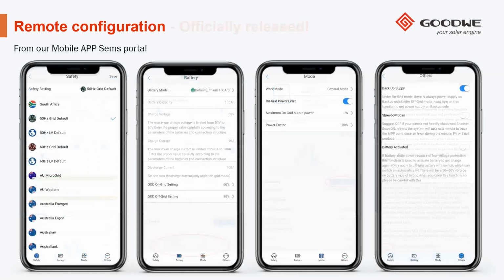From there, you'll see most of the basic commissioning is available, but it's always recommended to commission your inverter on site, and this is only for if changes need to be made in the system. If we have, let's say, bad weather and grid outages on the way, you can come here to adjust your SOC levels, you can adjust your work mode, you could even change the country code if needed. So you'll see all the different selections available on the application.